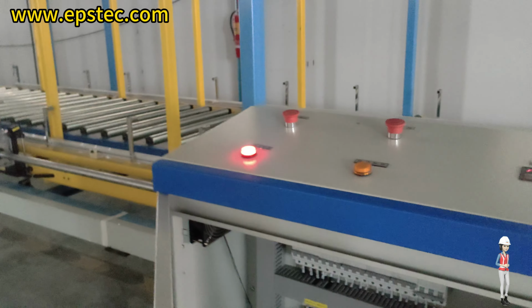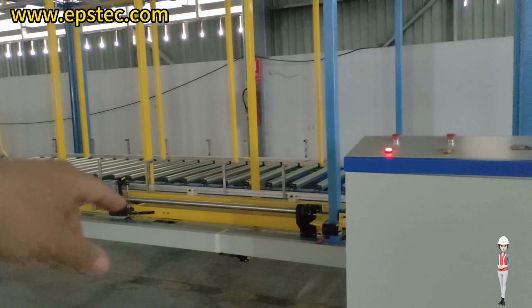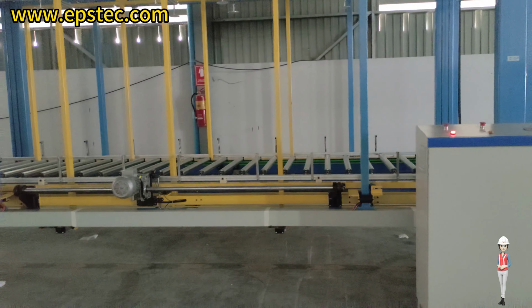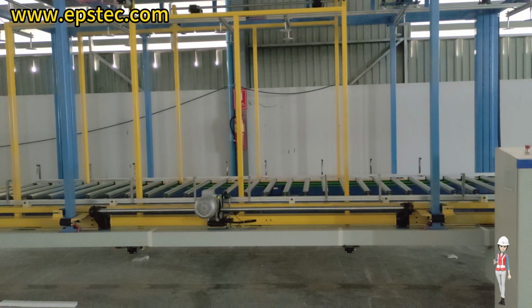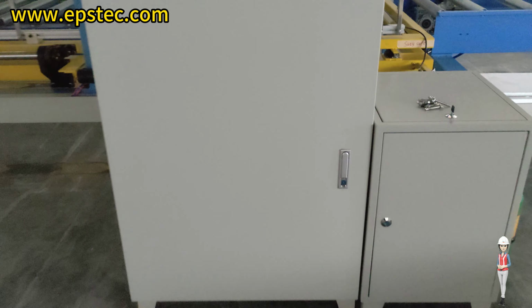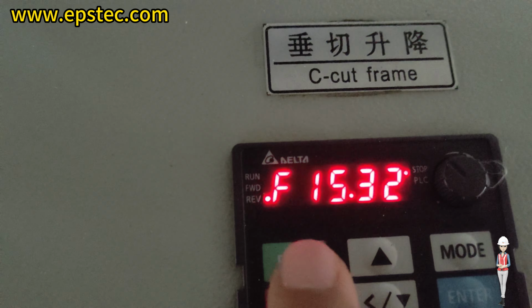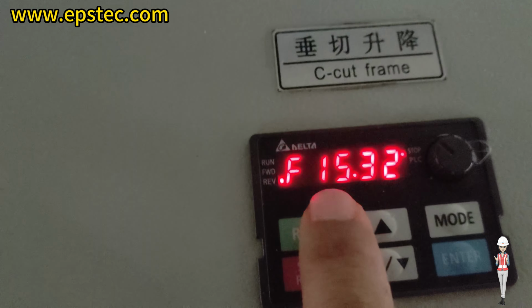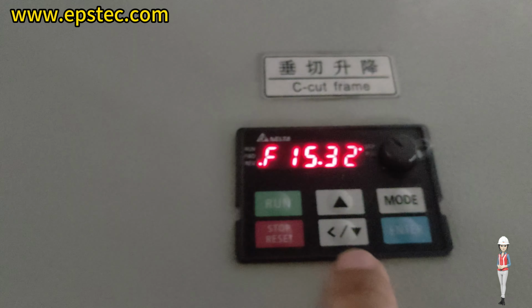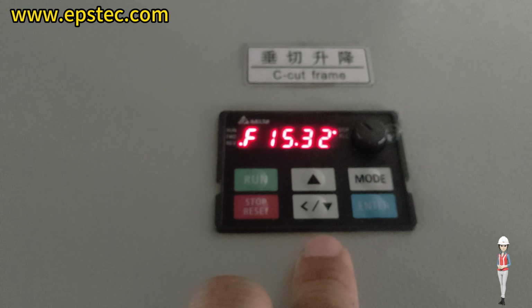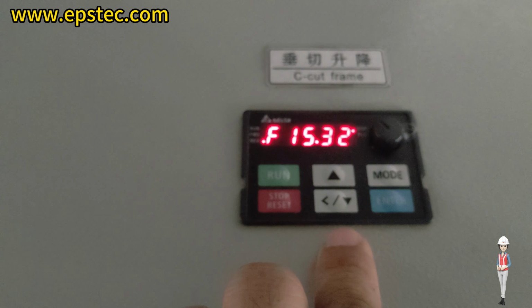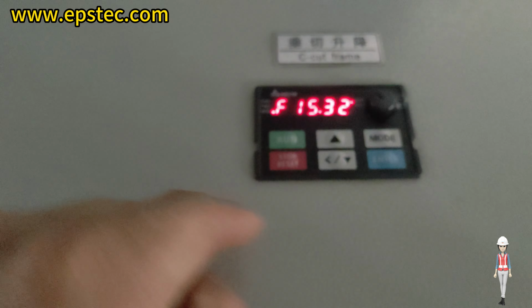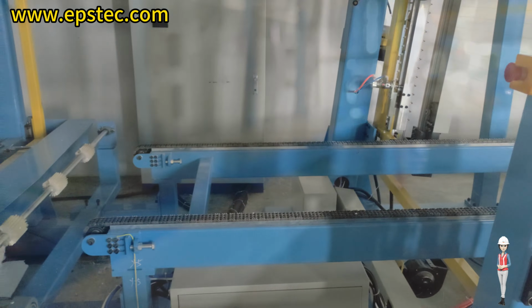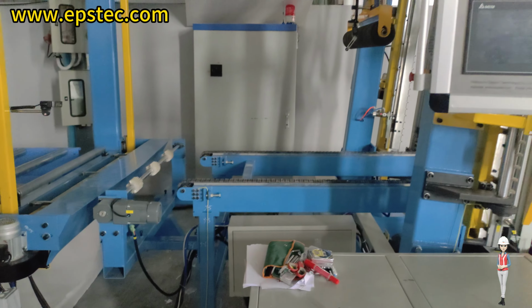5. Alarm handling and feedback. For occasional alarms on the EPS cutting line, the operator can try to restore its normal operation by cutting off the power and then repowering. If the alarm occurs frequently, not only record the alarm code, but also observe the operating condition of the EPS cutting line, collect related data, and immediately feedback to the debugging personnel or manufacturer. Follow the guidance of the debugging personnel, carry out repairs or replacements of the drivers on the EPS cutting line, and if necessary, return to the factory for handling.